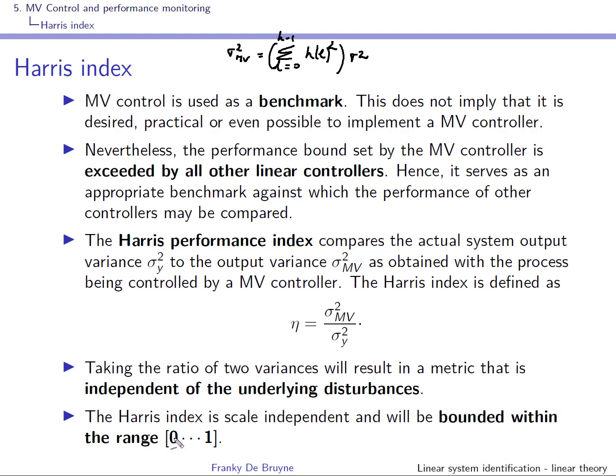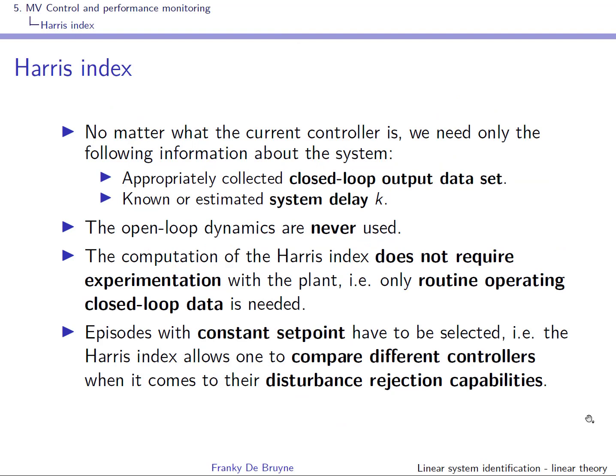The Harris index is computed from closed-loop output data with the controller you're benchmarking. The only thing you need to know is the delay in the system — you don't need to know G of Q. No experimentation is required. You can use routine closed-loop operating data while your process is running in production.